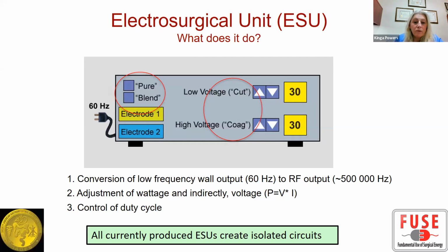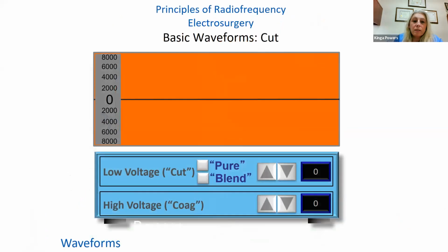So let's go over the cut, coag, and blend modes just to make it very clear. This is a picture of a generator in blue, and it can produce different waveforms of current. We're going to set it to either cut or coag. The orange is an oscilloscope, which basically shows the amount of energy and current that goes through a circuit, and I will show you the differences between cut and coag. Most American ESUs use these designations: cut, coag, and blend. We'll start with the cut mode. I'll set it on pure cut, and we'll dial it up to 30 watts.